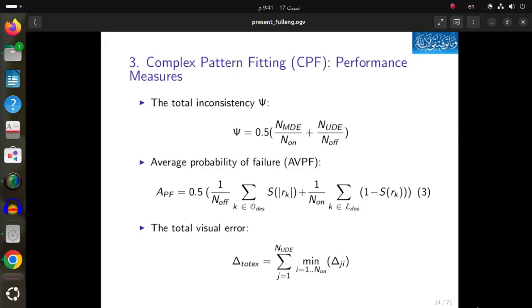Alternatively, we can use the visual error. It's not important which locations are excited and which are not. What we really care about is those locations that have been excited by mistake: how far are they from the intended phosphene locations? If they are close to them, the visual error is small. Of course, the visual error can again be compared based on worst case or best case thinking, or computed based on probabilistic thinking by comparing delivered currents to the intended thresholds to achieve the goals of each location.